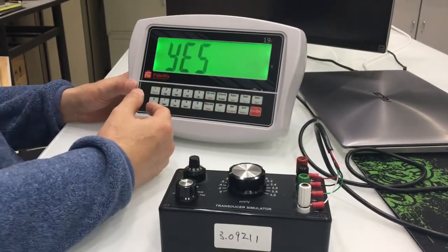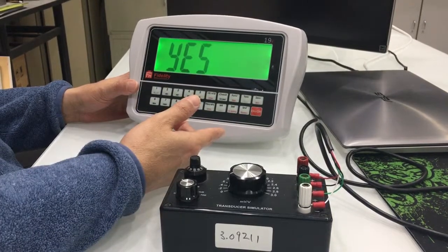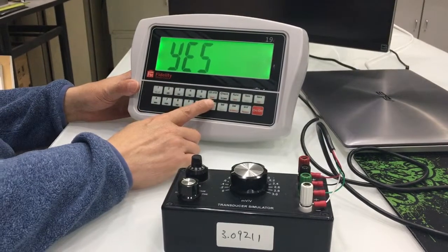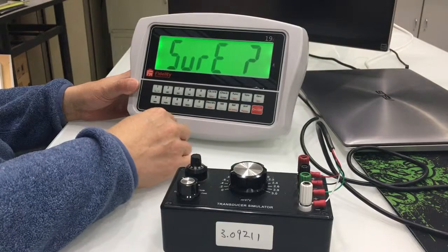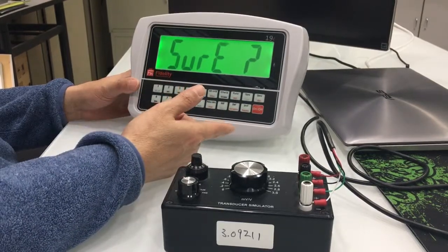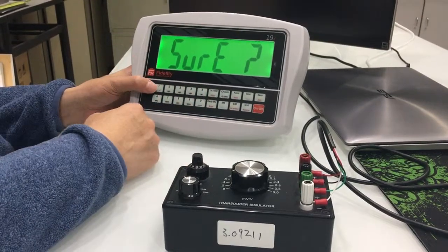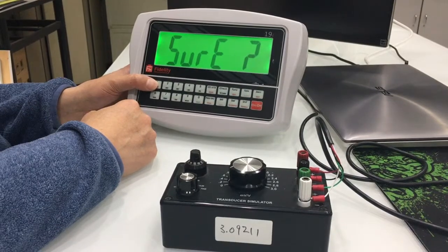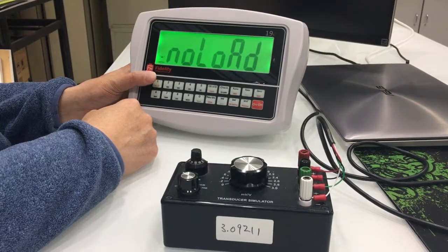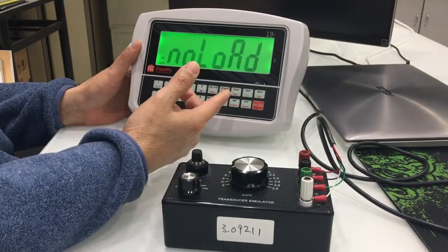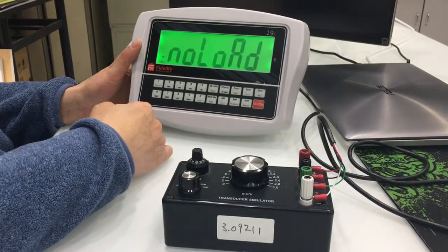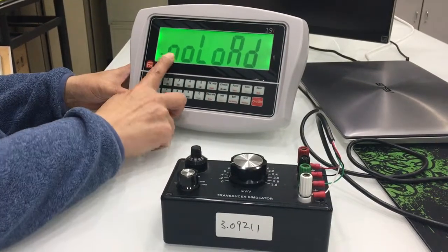Now the indicator asks us, do we want to go further for the calibration? We say yes, enter. And then the indicator confirms again, are you sure? I said yes by pressing numeric key 1.